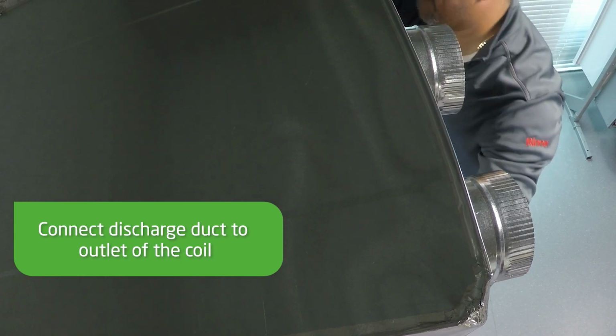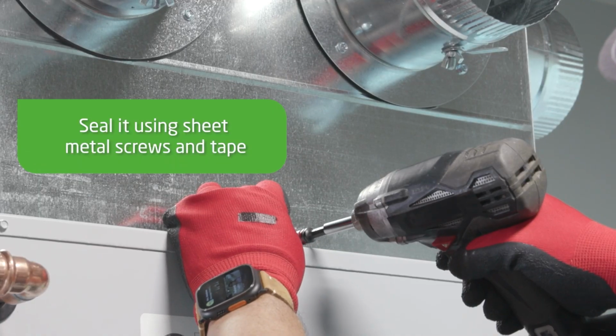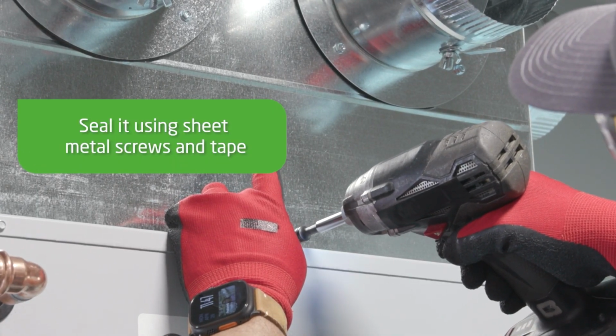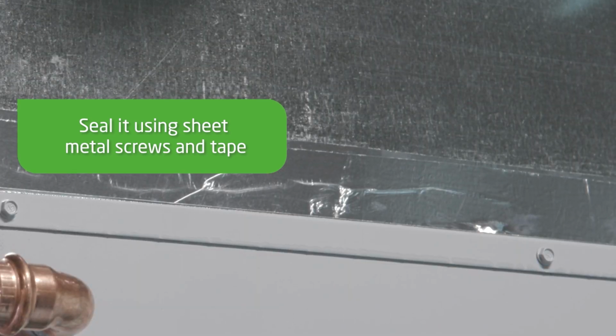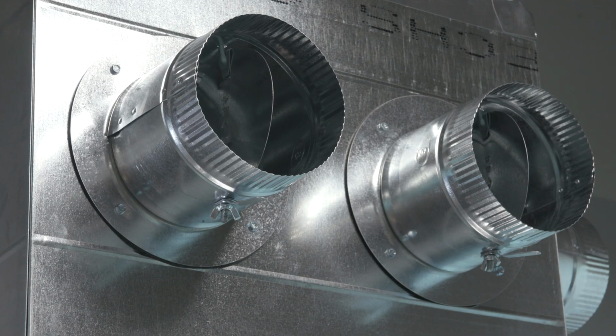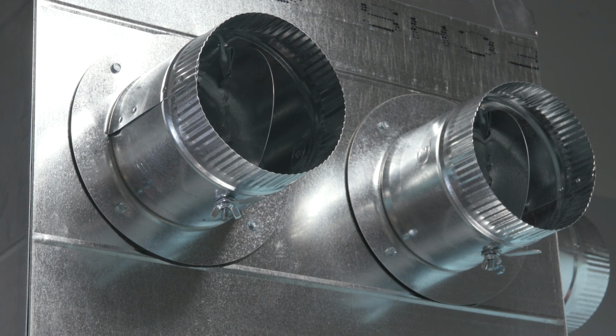Connect the discharge duct to the outlet of the coil and seal it using the sheet metal screws and tape. You will have to make adjustments to the existing ductwork based on the size of the coil. We have pre-cut ours for the purpose of this video.